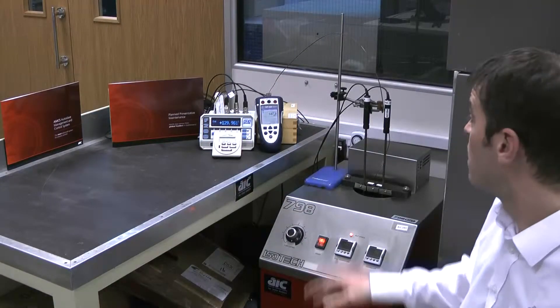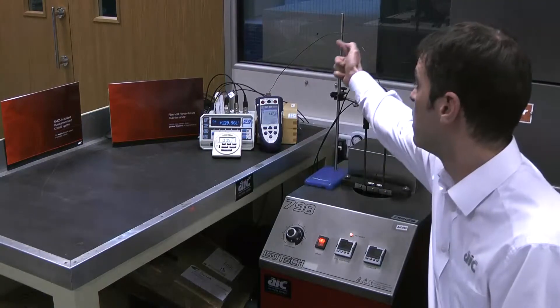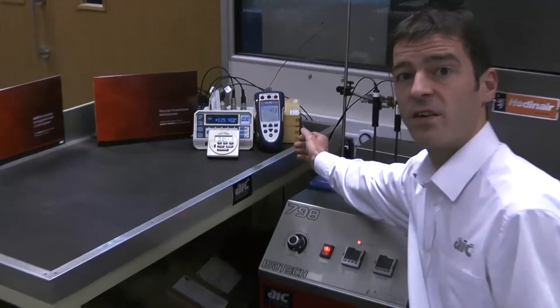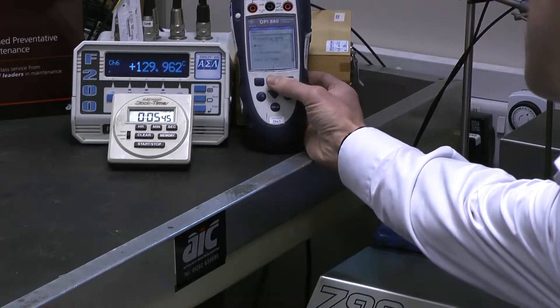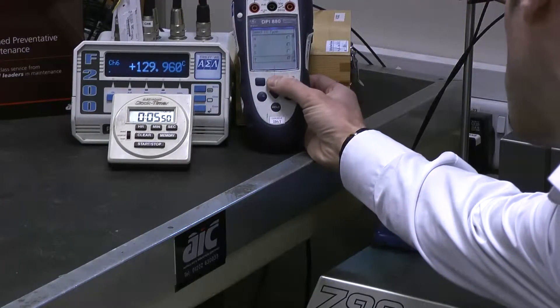The Type T thermocouple now has almost zero temperature gradient in it. It starts here, goes back to the instrument.